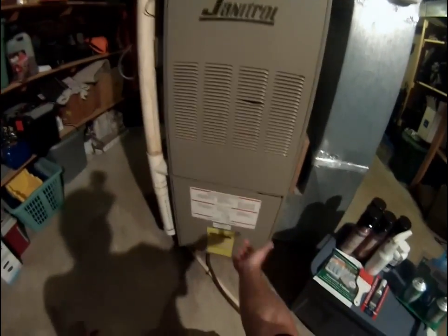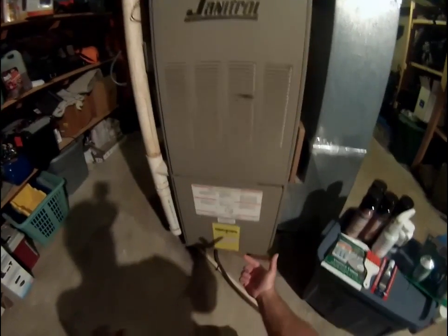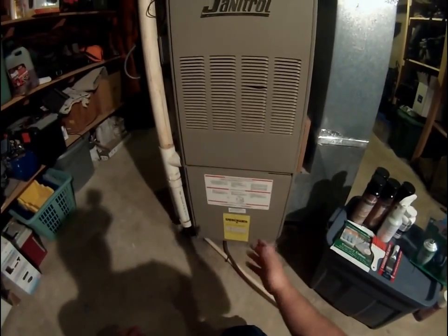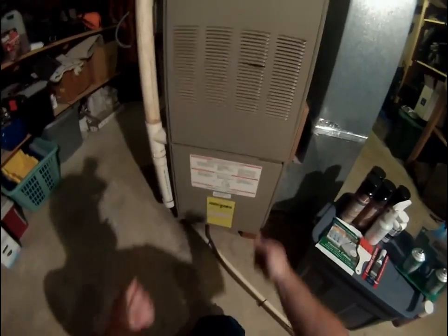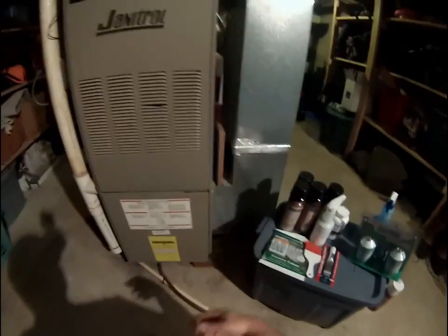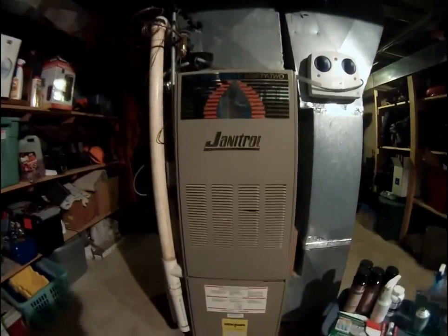But there is a secondary heat exchanger, which is almost like a radiator on a car, on most high efficiency furnaces nowadays. So you could take this out, pull the blower out, and then lay on your back and get under there, and you'll see that coil. And you can brush it off and clean it with maybe some of our coil cleaners as well.